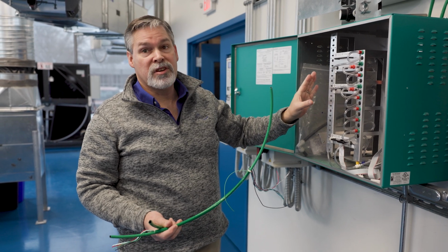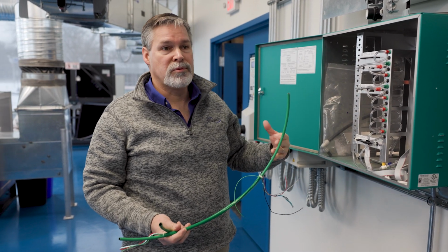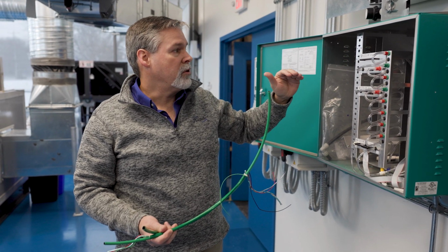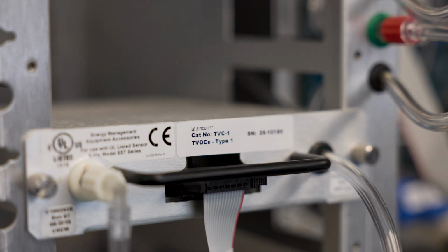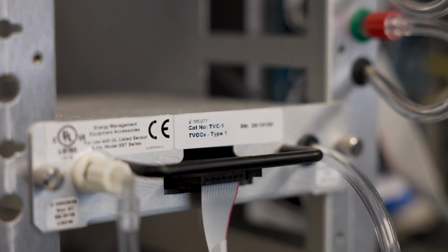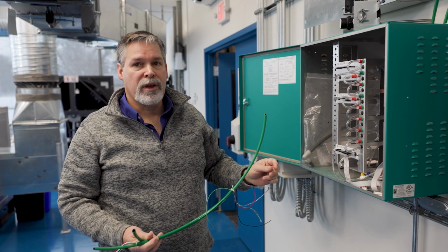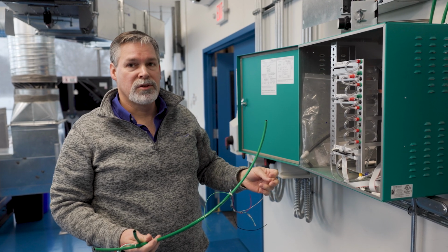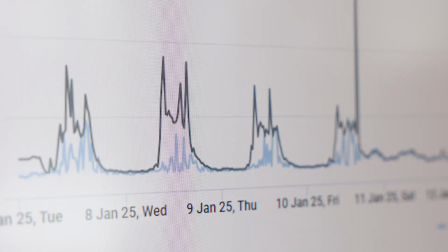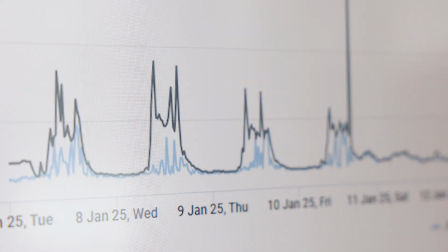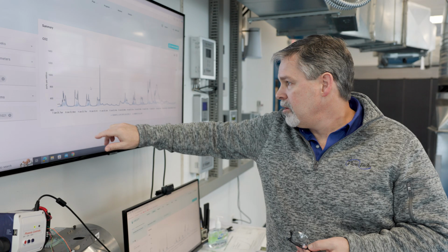Here that air sample is going to get analyzed for what happens to be on that particular project. So here we have a CO2 sensor, a dew point sensor, and a total volatile organic compound sensor. We can also do small particles, and carbon monoxide. We're using the air supplying that space as a reference to that space. That allows us to compensate for sensor drift. So if a sensor drifts 20%, the differential in those 2 readings is still going to be accurate.